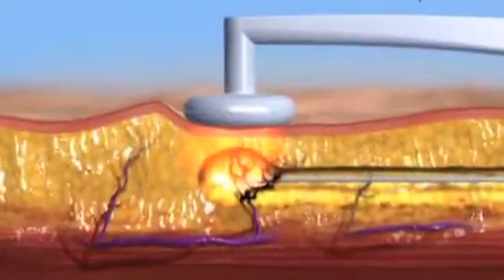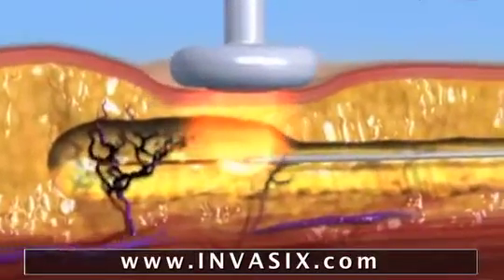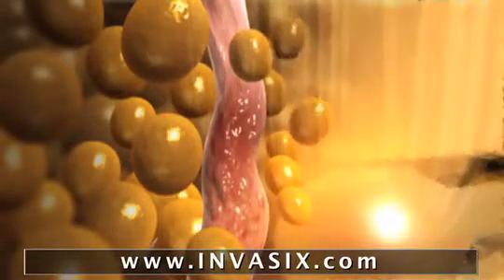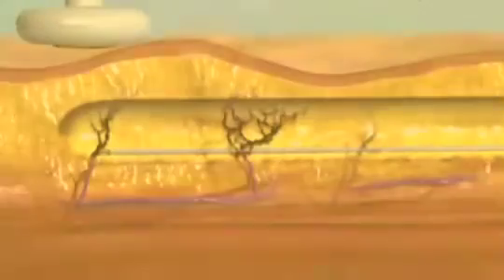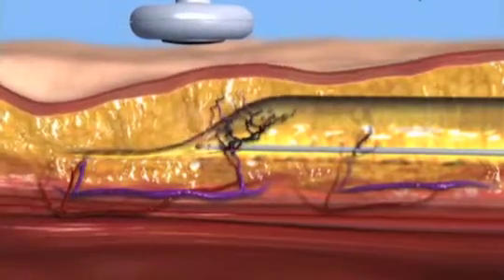The newest device I've been using is radiofrequency liposuction, made by a company named Invasix. In this device there's an internal probe and an external probe — it's bipolar radiofrequency, meaning radiofrequency energy travels from the lower probe to the upper probe, causing fat cells to be disrupted via a heat mechanism. It also tightens the skin through heat, similar to laser liposuction, though the radiofrequency proponents say it's a little bit safer.